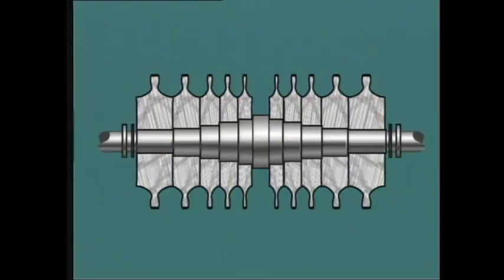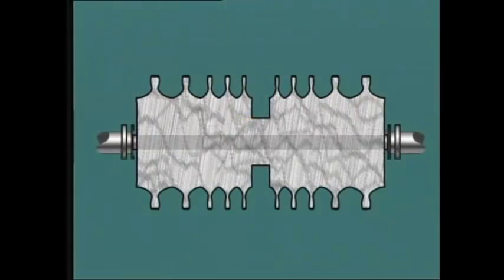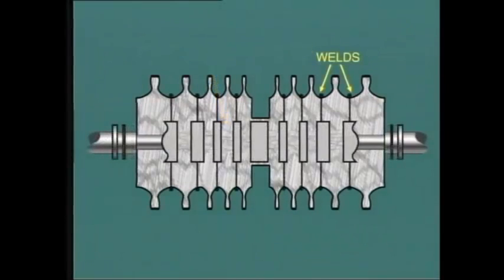A problem with this type of construction is that in some cases, steam may leak along the shaft and cause distortion due to differential heating as well as a loss of efficiency. To overcome this problem, in modern turbines, the discs and the shaft are forged in one piece and then machined. Yet another method of building up the rotor is by welding discs together and so eliminating the shaft.